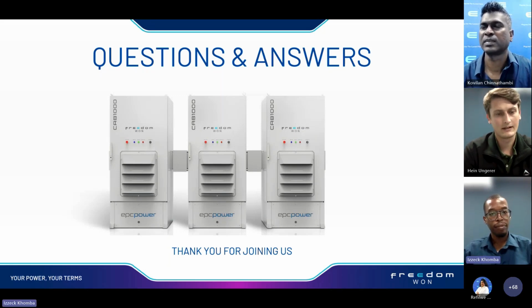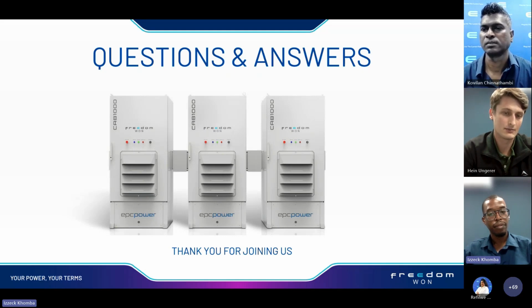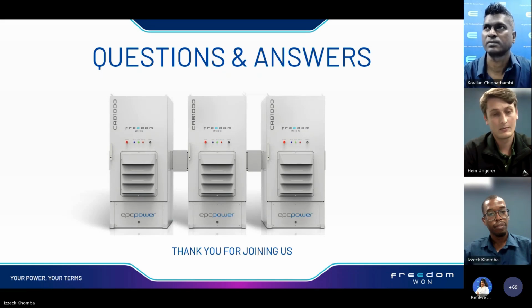Just to add to that as well, this 7 times motor power rating for the inverter size is something that came from probably people's experience with ATES systems, where the inverter would trip on converter L over current when a motor starts, which I'm sure we're all familiar with. The difference with the CAB1000 is that if the maximum transient load is smaller than the inverter rated capacity, the inverter will not trip. However, the bus voltage will drop to supply that reactive power, but the inverter will just pick the bus voltage back up once the transient spike is finished. So that is the big difference here. Thanks, Harry.